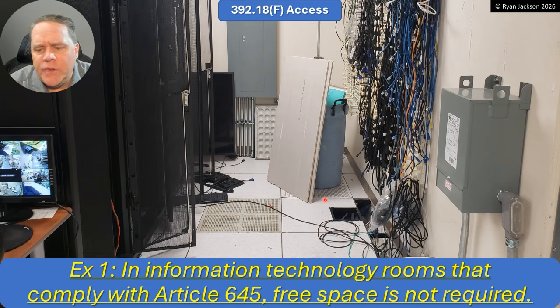Exception 1. In information technology rooms that comply with Article 645, the free space is not required at all. That's what I think the exception is trying to say. And I guess that makes sense because when I think of an IT room, you could have a cable tray up in the ceiling, certainly, but you're just as likely to have one underneath the raised floor. And, you know, you might not have a 12-inch dead space underneath the raised floor to get that 12 inches of clearance. And why should it matter? Because the obstructing item above the cable tray, the floor, is removable. So what's the issue, right? So I don't think I would require any free space in an IT room.